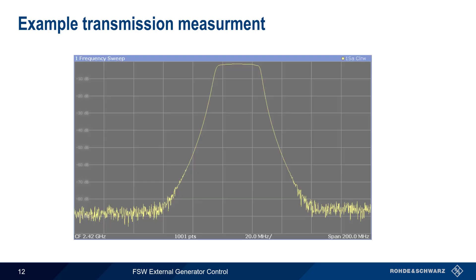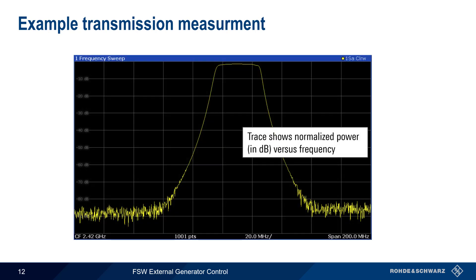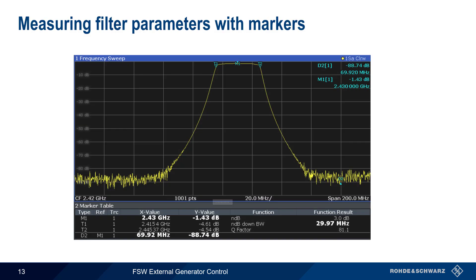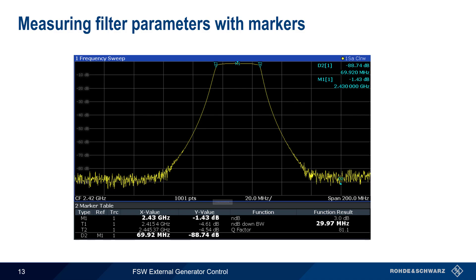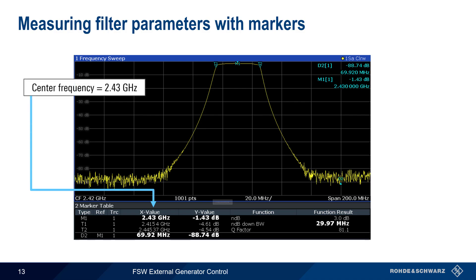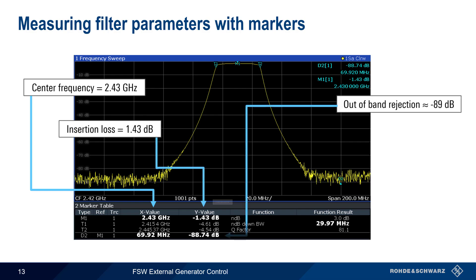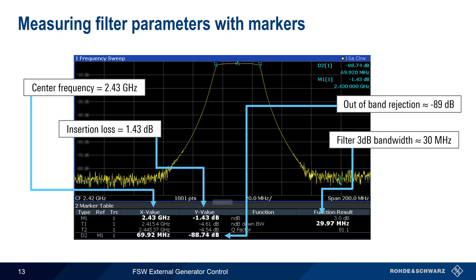On the FSW, we can see the results of a bandpass filter measurement. The trace shows normalized power in dB versus frequency. With normalization on, the displayed values are all relative to a normalized value of 0 dB. Enabling markers allows us to easily determine numerous filter parameters, such as the center frequency of the passband, the insertion loss within the passband, the level of attenuation or rejection outside the passband, and the 3 dB bandwidth of the filter. Note that Q, the quality factor of the filter, is also automatically calculated and displayed by the FSW.